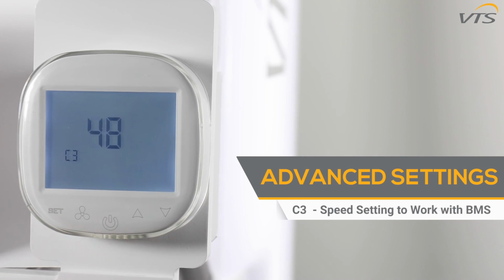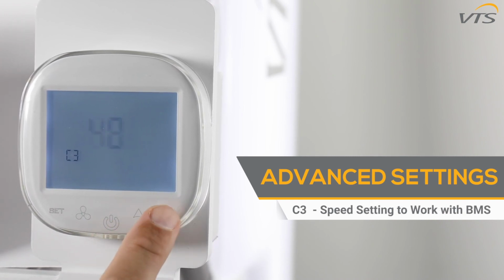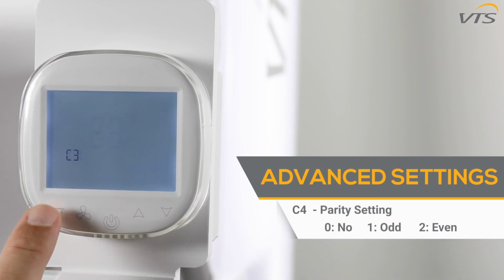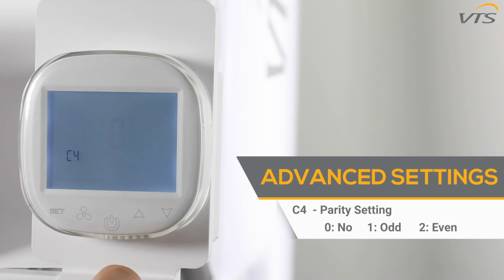The C3 function gives you the ability to change the speed setting for the controller to work with the BMS system. The C4 function allows you to change the parity setting between the controller and BMS system. 0 is no, 1 makes it odd, and 2 makes it even.